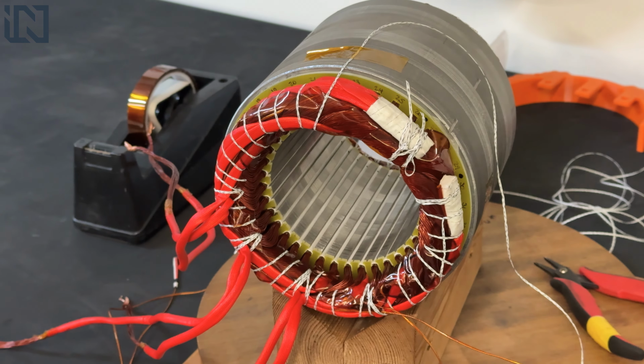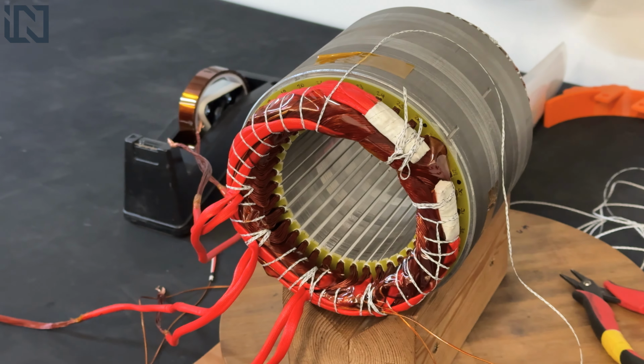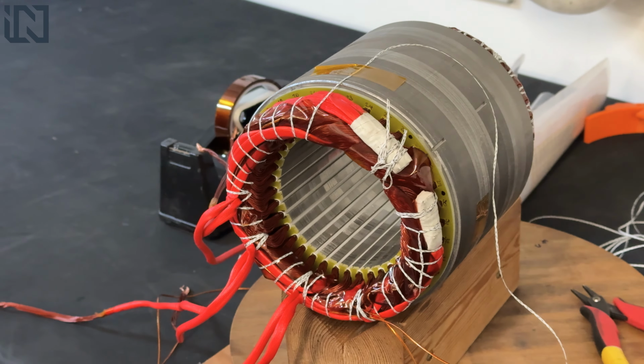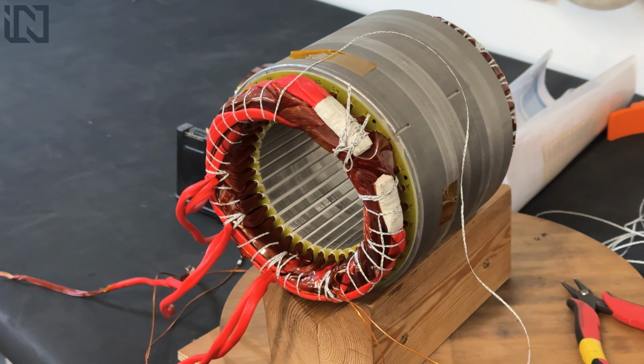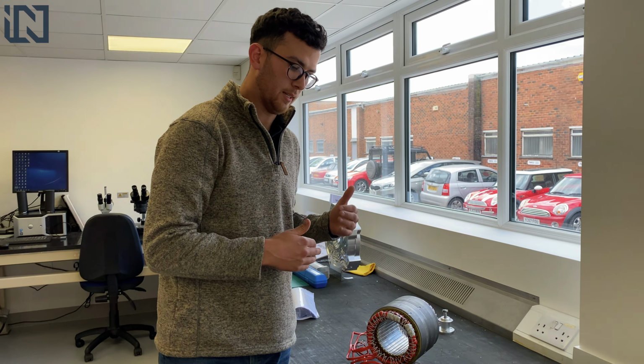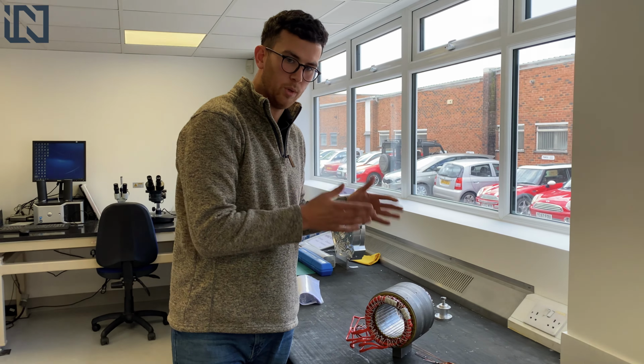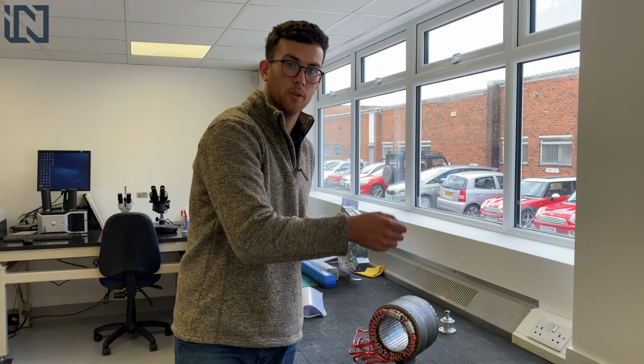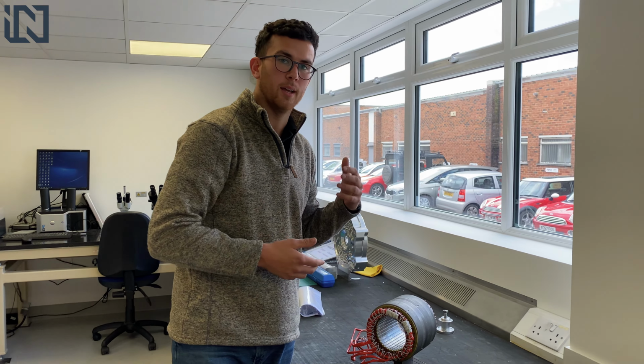Now we've seen what happens with the actual test results, let's talk about the motor. When we come to actually doing the motor itself, we take these coils and we put them into the motor. Now by doing this resistance and inductance testing, we can test: have we got the right length of wire? Have we got the correct number of turns in the motor? Is it all going to work when we move to the final product?